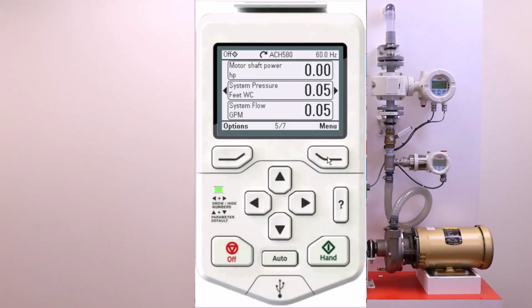The first thing we need to do, right now it's set up, let's just look at the keypad's display right now. The drive is off. I go into hand mode. The drive is going to accelerate up to 60 hertz. 60 hertz is my current speed reference. I can change that by going up and down arrows right now if I wanted to. The drive gets up to full speed. We can see our water column pressure, 38 feet. Shaft power in horsepower is 0.367, and gallons per minute is about 9.35. So I can stop this, and let's start some programming.